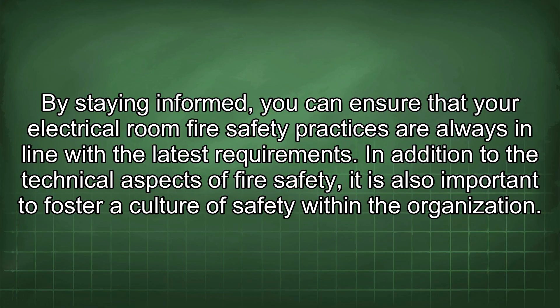Also, remember to consider the impact of environmental factors on electrical room fire safety. Temperature, humidity, and dust can all affect the performance of electrical equipment and increase the risk of fire. It is important to maintain proper ventilation and temperature control to prevent overheating and condensation. Regular cleaning can help remove dust and debris that could ignite or interfere with the operation of fire protection systems.